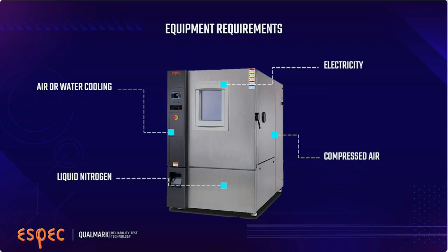Water cooling can be used instead of air cooling. In most cases today, our customers are not simply using city water to do this, but are purchasing a dedicated water chilling system. There are several types, and selection is dependent on your location and other factors.